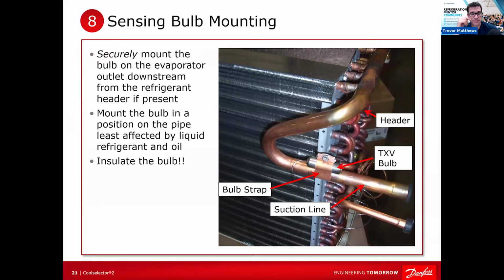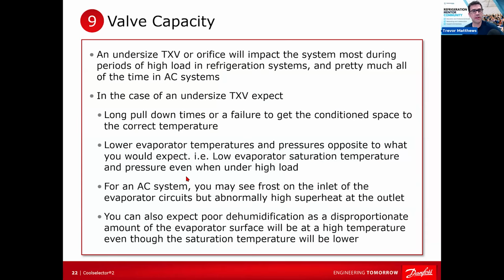I've had guys argue, like guys that argue over 0.1 inch of static per 100 feet or something like that, right? There's no fixed and fast rule. Yeah. The big thing is when I started doing electronic valves, all of a sudden the bulb needs to be insulated. And then like in refrigeration, the air temperature is the same temperature. Well, no, the pipe temperature is not the same temperature as the air temperature. No, it's not. If it was, you wouldn't have a heat transfer. But it's close enough, I guess. It is. Yeah, okay, fair enough.